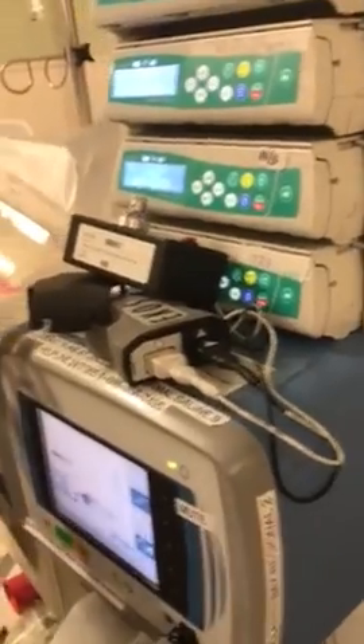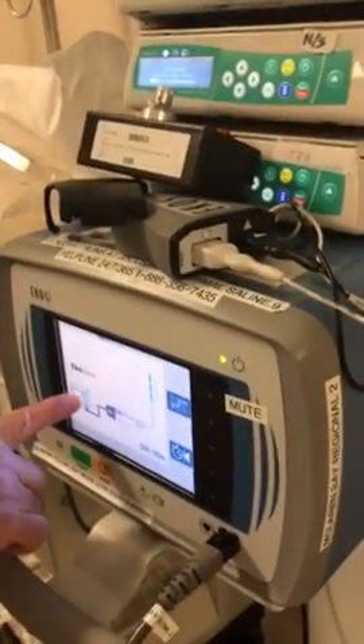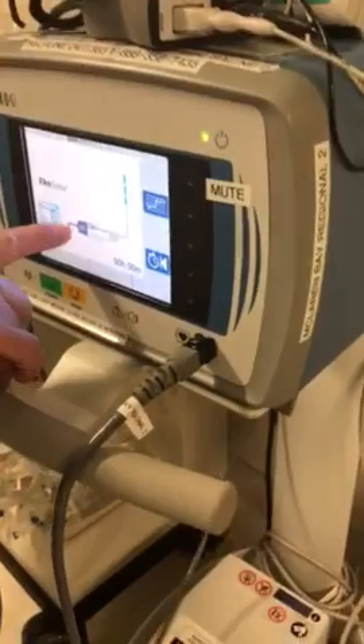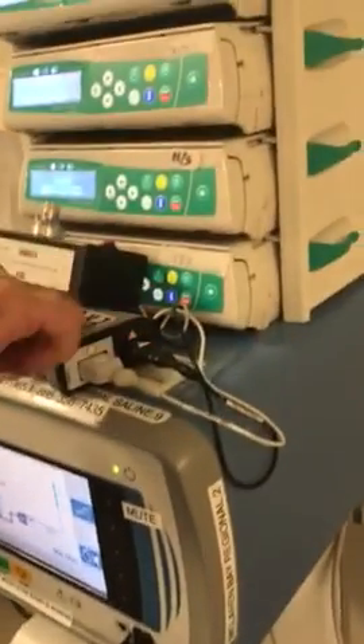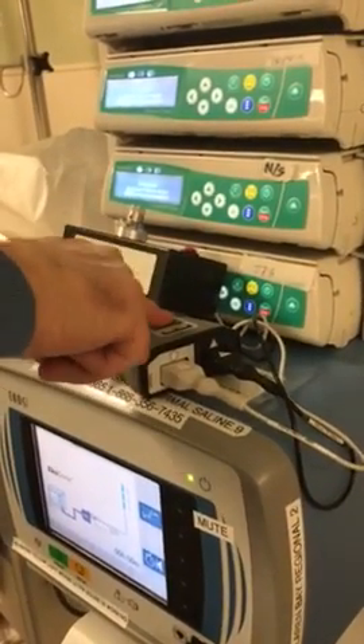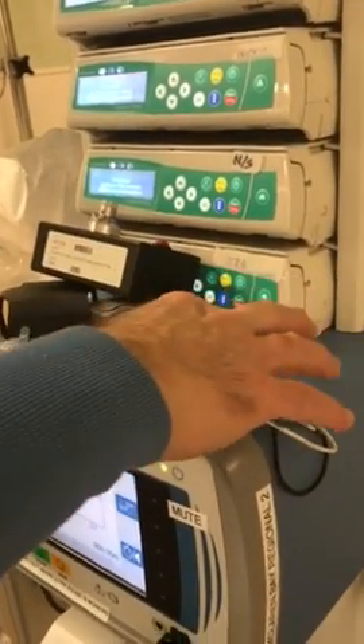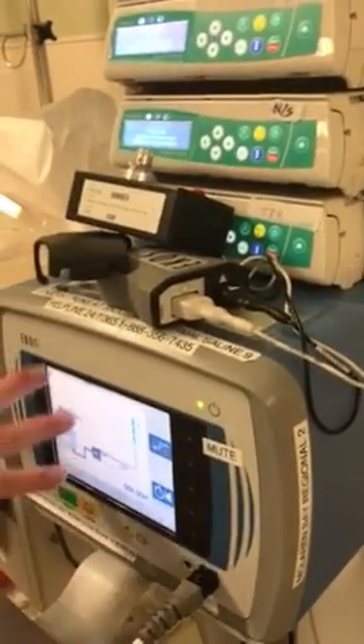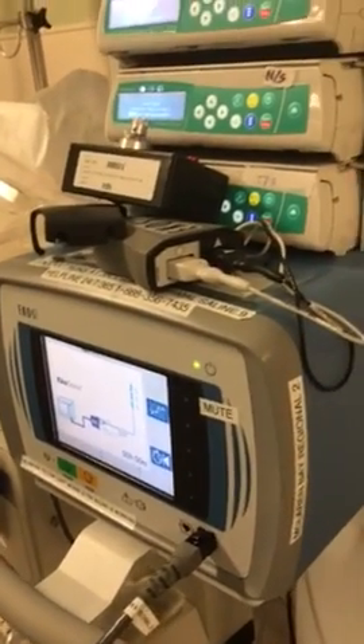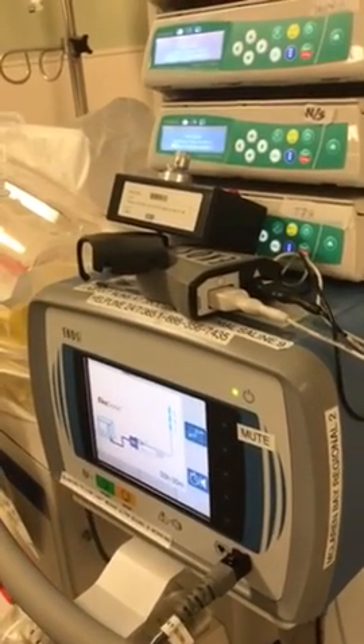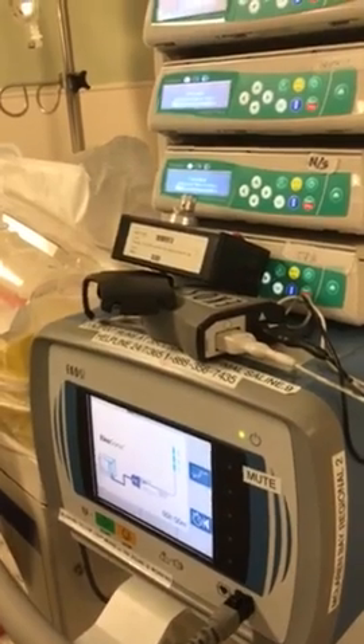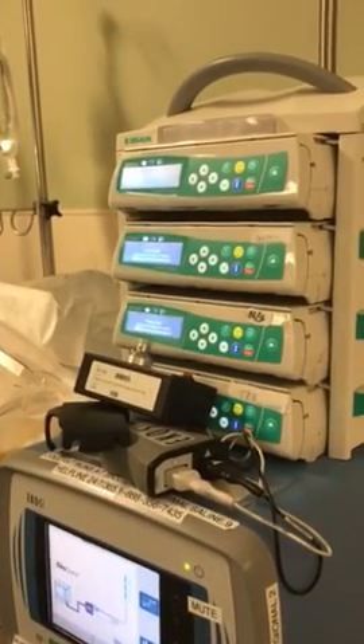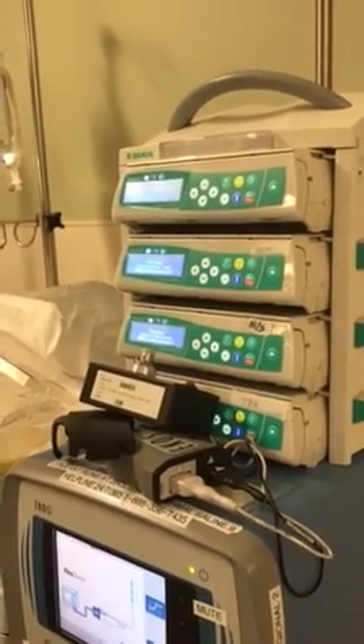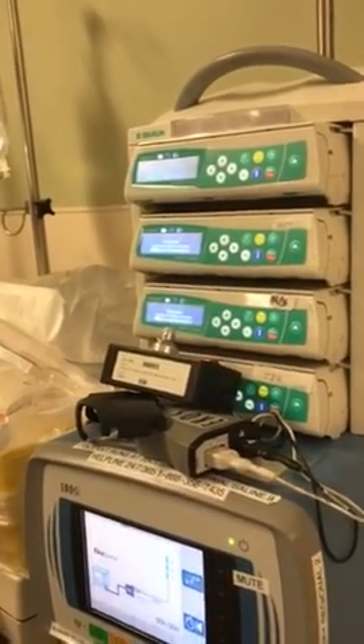That's now connected. When you look at the whole big blue box, the big blue box is the control unit. The gray cable is the CIC, the connector interface cable, and you connect these two. Once you have them all connected, you have your fluids: 35 cc's per hour for normal saline, your TPA, say 1 milligram per hour, and whatever you prefer to run through the sidearm sheath, whether it be heparinized saline, protocol, and so forth.